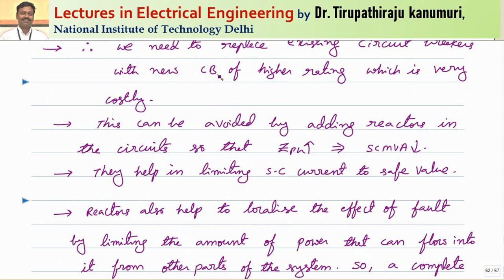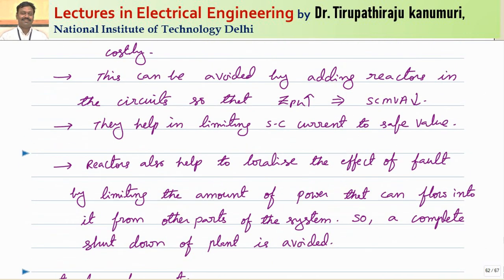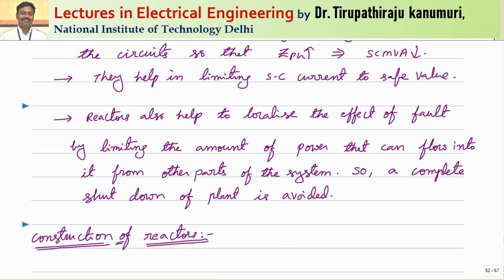The goal is to continue using existing circuit breakers even when new generators are connected to the system. The solution is to increase the denominator — that is, by increasing Z per unit — so that short circuit MVA can be maintained constant. Even though the system's full load MVA increases, if Z per unit is increased, the short circuit MVA will remain within the limit and we need not replace the circuit breakers. To increase Z per unit, reactors are inserted in series with the system.